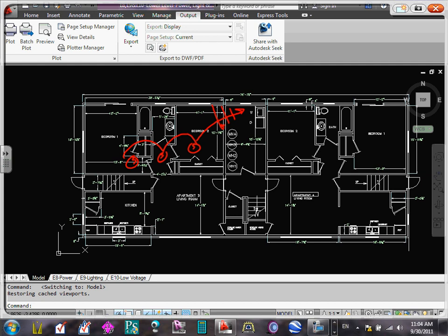And in between, you're going to have a hot, a neutral, and a ground, right in between these two. Hot, neutral, and ground, because the smoke detectors that we're using are going to be power devices. They're actually a smoke detector, a horn, and a strobe all in one, unlike low voltage, where we split the detector from the horn from the strobe. Any questions about that?